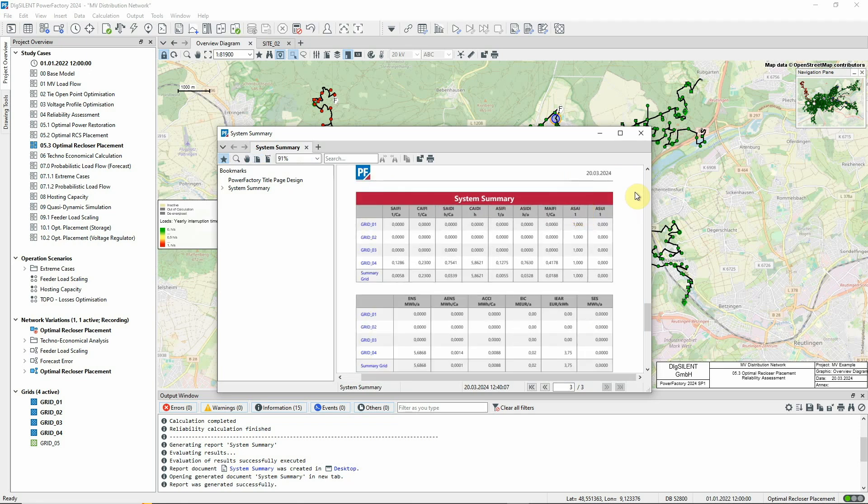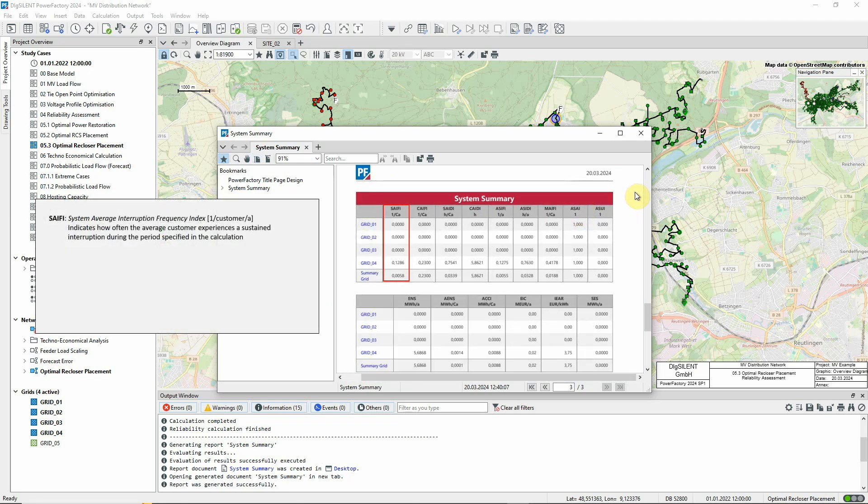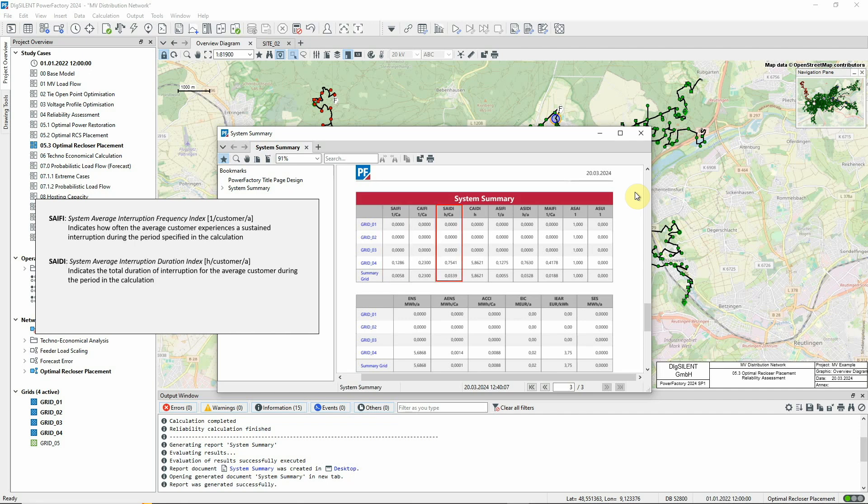Commonly used indices include SAIFI, which is the system average interruption frequency index, SAIDI, which is the system average interruption duration index, and ENS, or energy not supplied.